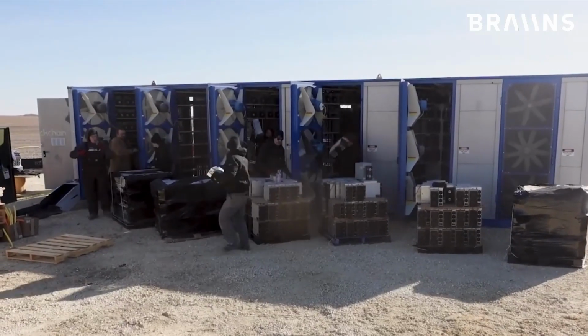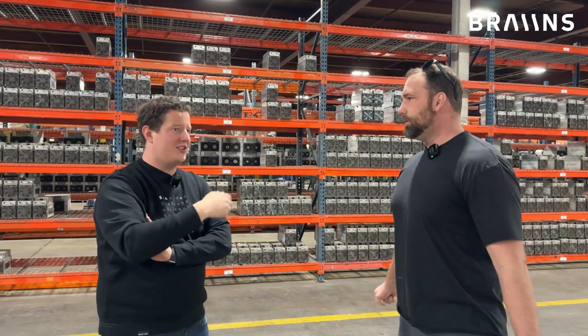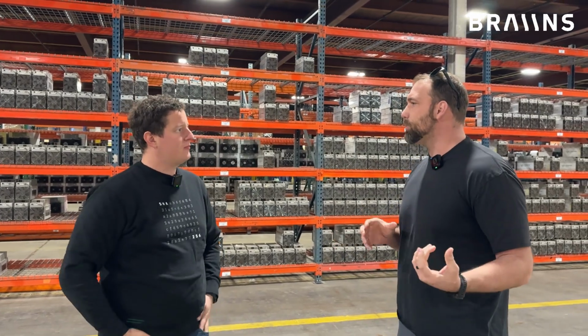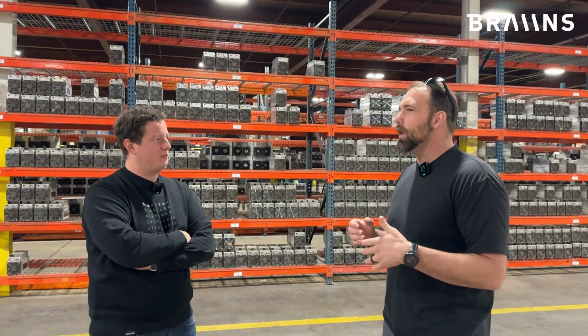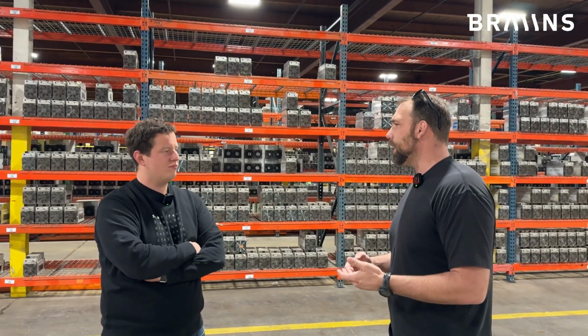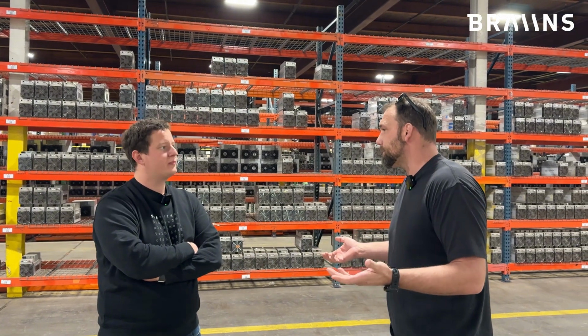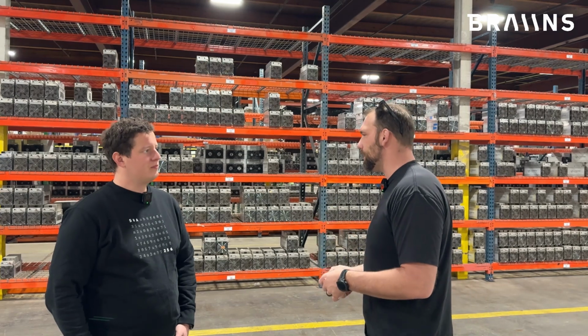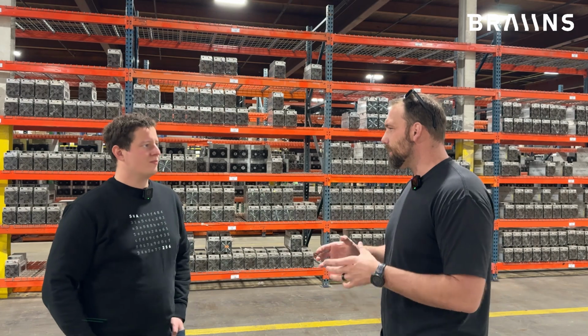You're experts in air cooling, you have all the processes set up. Why would you say, okay, let's try hydro? You see the manufacturers pushing to a better cooling technology, yes, but a lot of the early systems didn't work. Originally, they were using evaporative cooling instead of dry coolers because it's less expensive. You can do glycol loops or other loops if you're dealing in freezing areas like up in North Dakota. Water dissipates heat better than a glycol mix, so you have to make sure you get that right.